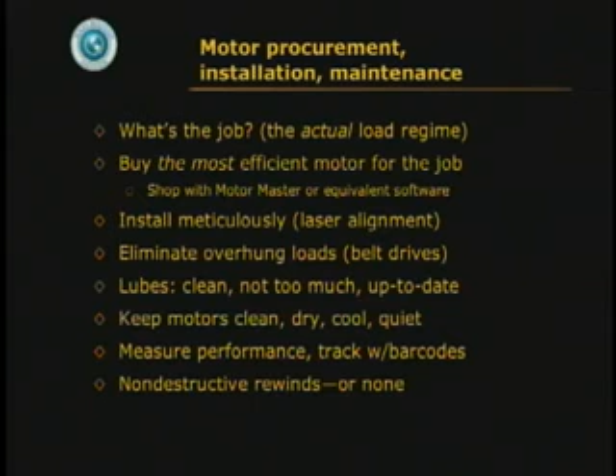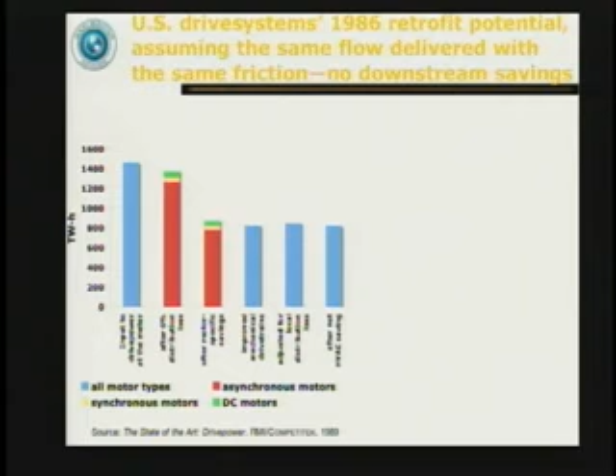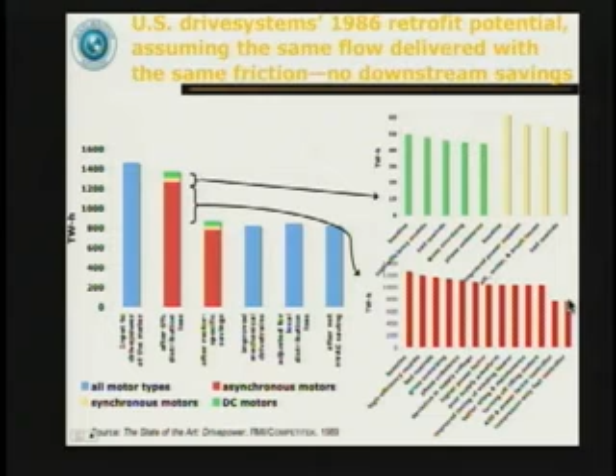But this kind of systems analysis reveals something very interesting. If you look at the input power to motors in 1986, it hasn't really changed proportionately much, and then you factor out the distribution losses and motor-specific savings, which I'll get to in a minute. You can save more with mechanical drivetrains and so on, but the motor-specific savings are this big gap, and they, for DC motors and synchronous motors and induction motors, have lots of terms to them. We were able to scope the uncertainties and show how much you saved by accumulating all these measures. Remember, almost all of those are left out of the conventional retrofit. So what you end up with is a very large saving at very low cost.